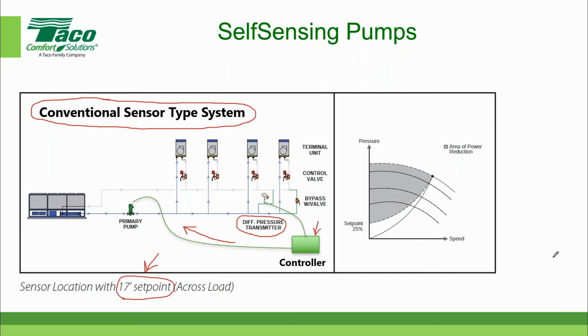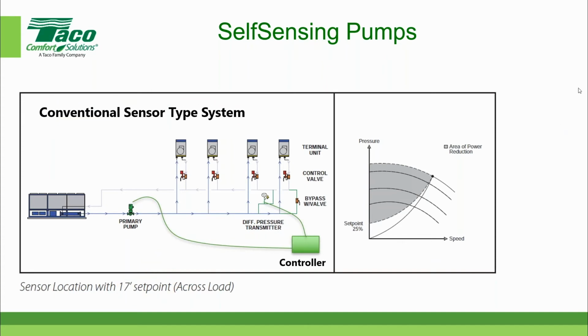That's excellent. The pressure differential is made up of 5 components. So in this case, the flow, let me erase some of these lines here so that I can draw some new lines in here. So if you'll notice, the pump supply water is going down this line right here, and then it gets to this point. The flow continues along, goes through the terminal device, in this case a fan coil, a control valve, the bypass is closed, so then it goes across here.